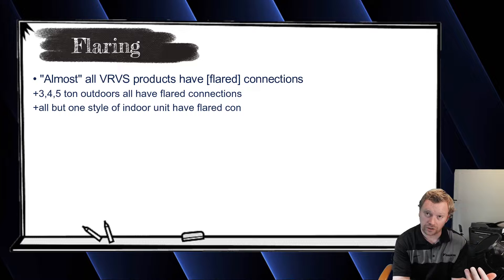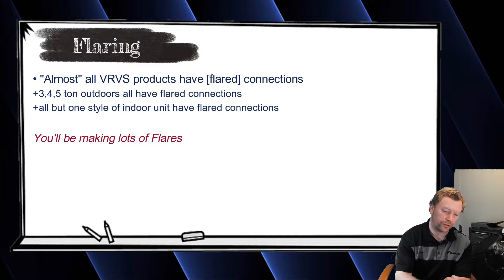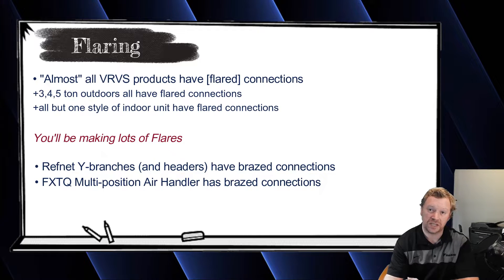The first thing I'd like to talk about is flaring. Almost everything on VRVS, just like mini splits, is a flared connection. Your outdoor units are all flared connections, all your indoor units are flared connections. The only brazing you're really going to have to do is on your Refnet Y branches and the FXTQ multi-positional air handler. That's pretty much the only brazing you're doing — everything else is flared.